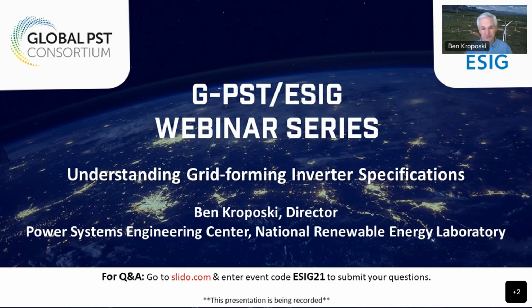Is that enough for the protection system? You probably are going to have to retake a look at your protective relaying to see if that is adequate for identifying fault conditions. There are other ways of addressing the lack of fault current from inverters, including adding synchronous condensers into your grid or repurposing some of your synchronous generators.